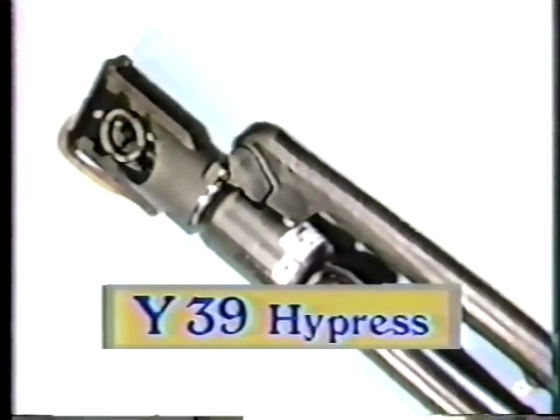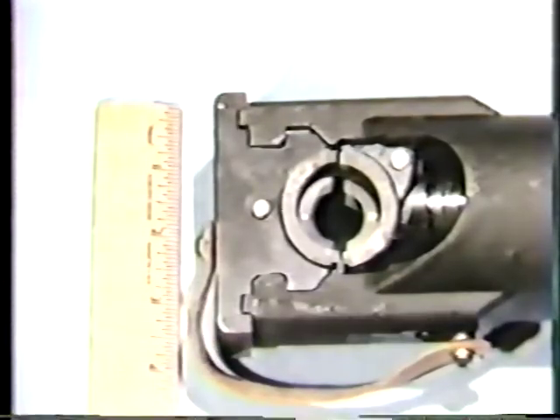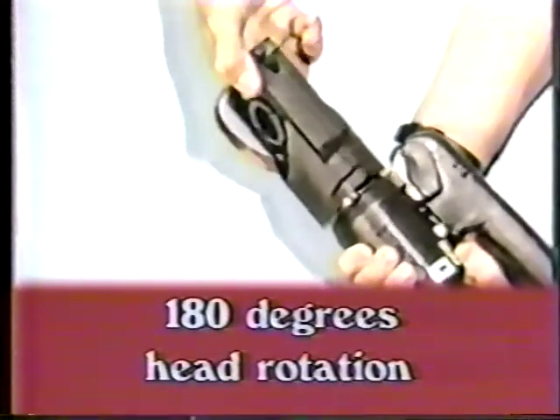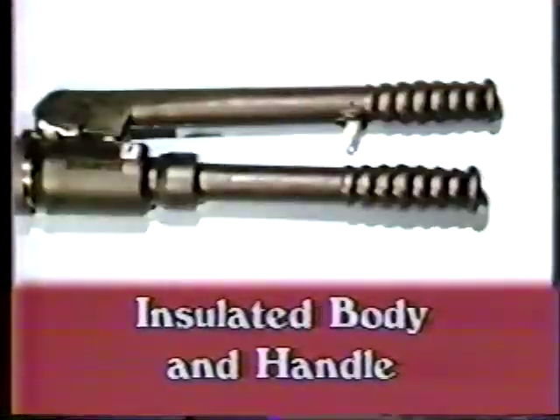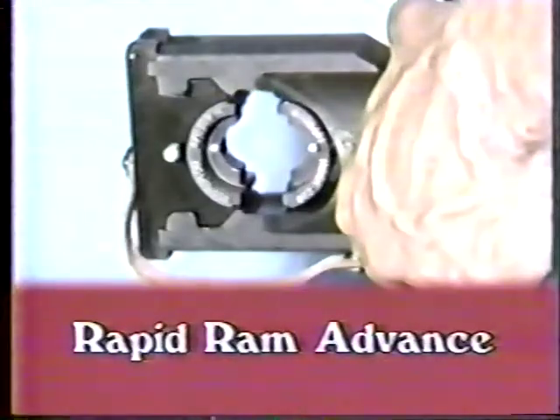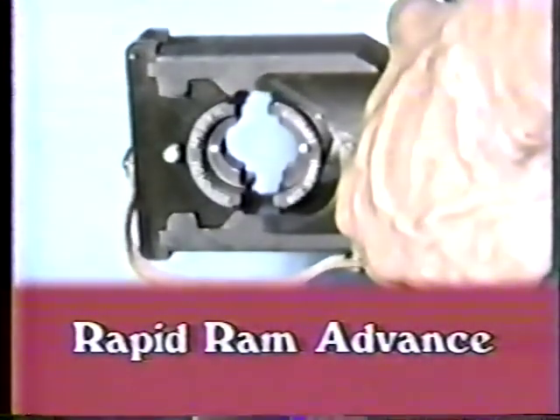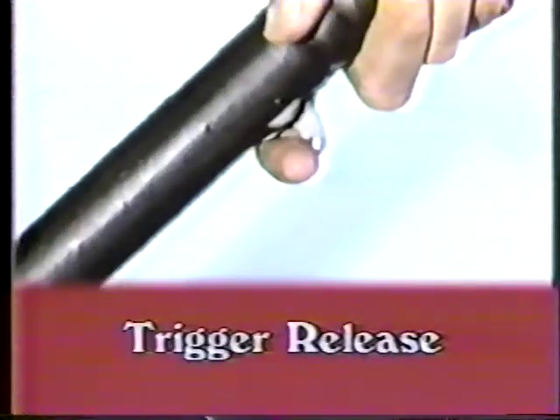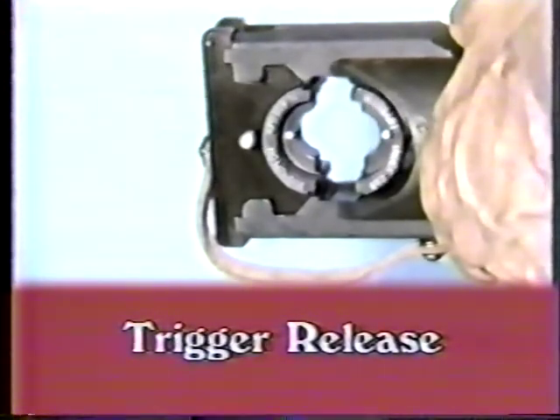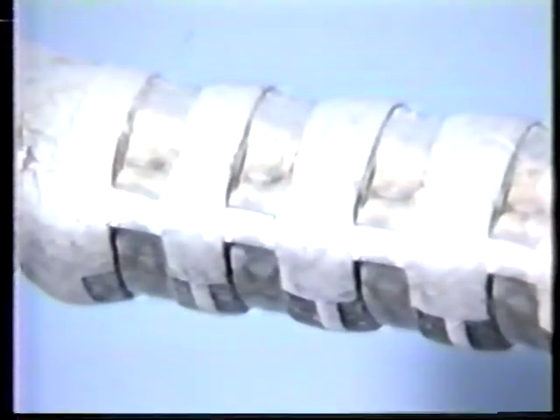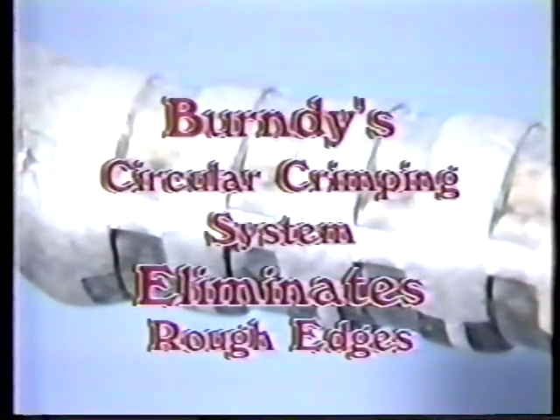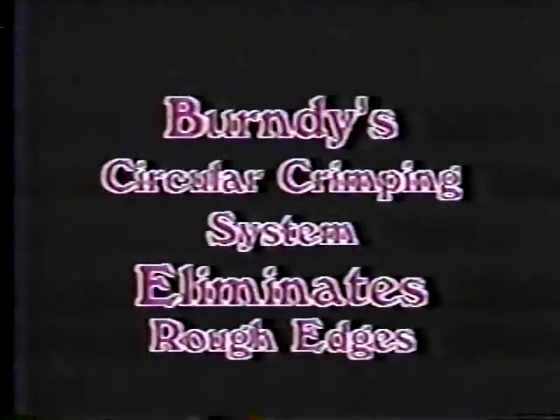For example, the smallest head in the business, suitable for use in a 4x4 wireway, 180 degrees of head rotation, insulated body and handle, a rapid ram advance to quickly engage the connector, and a trigger release to return the ram to a preset position. Unlike competitive designs, Burndy's circular crimping system provides a smooth crimp, which eliminates the additional labor required to remove rough edges that may damage insulation.